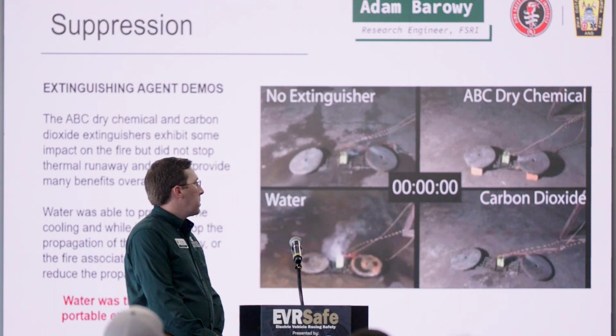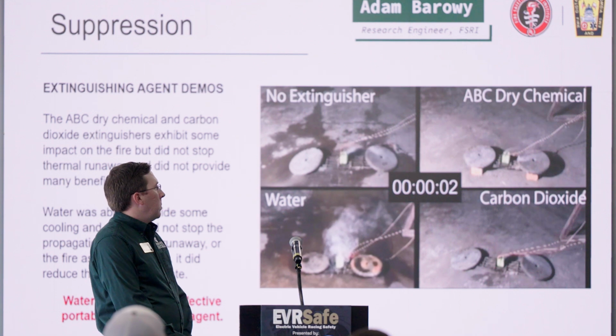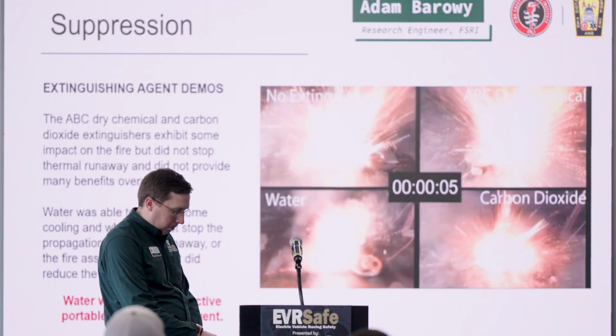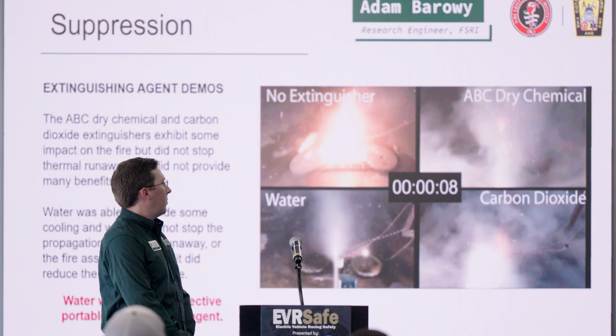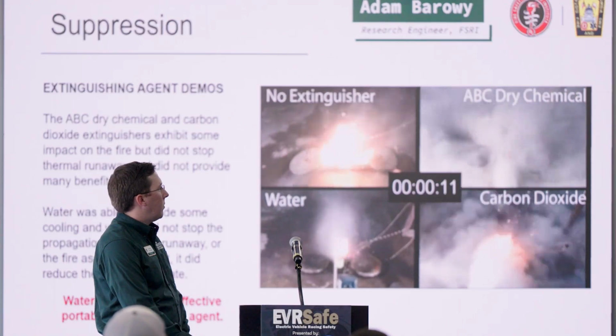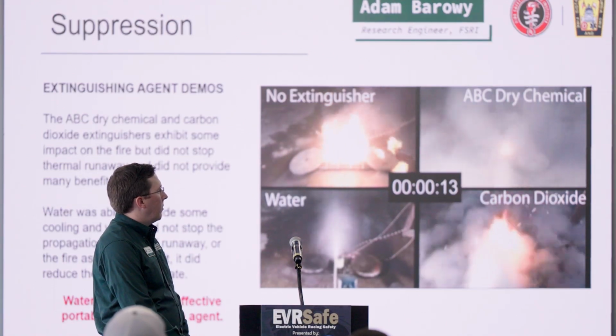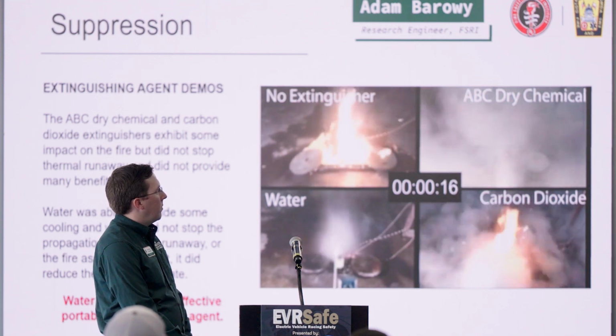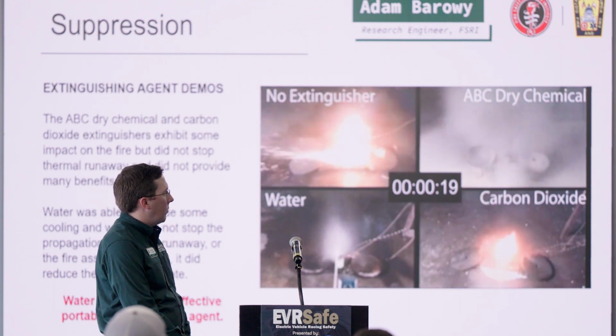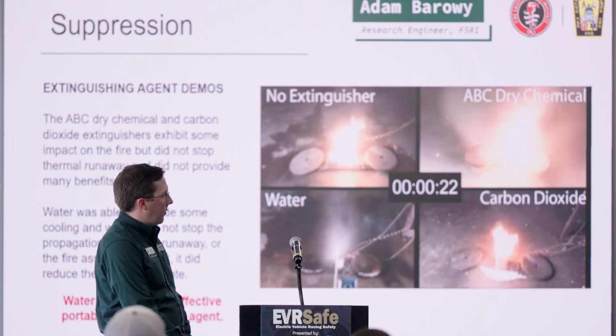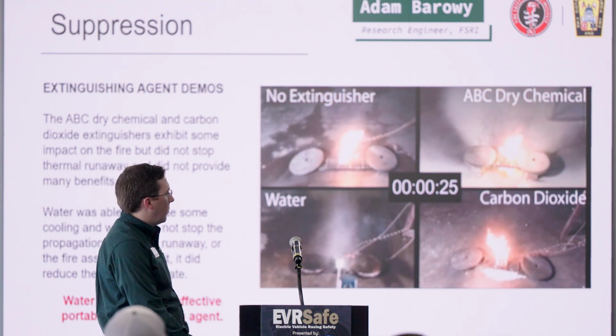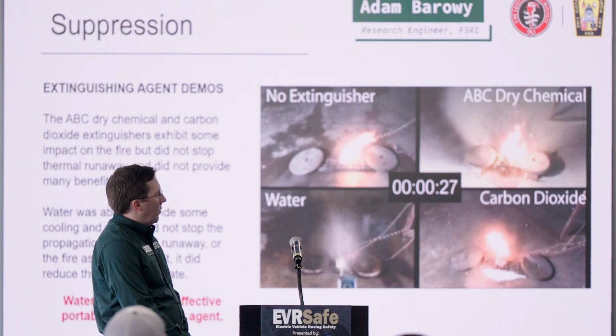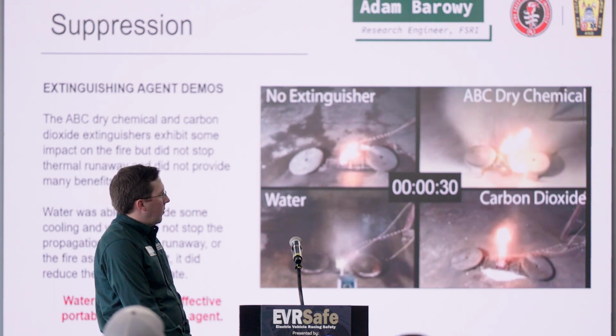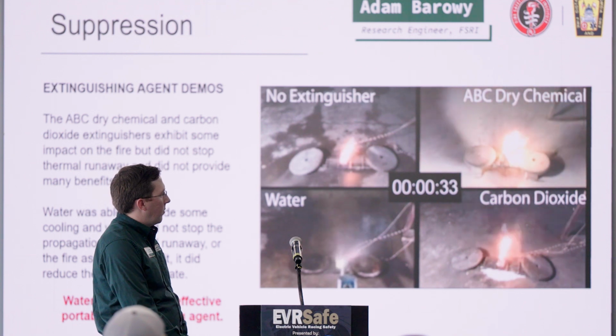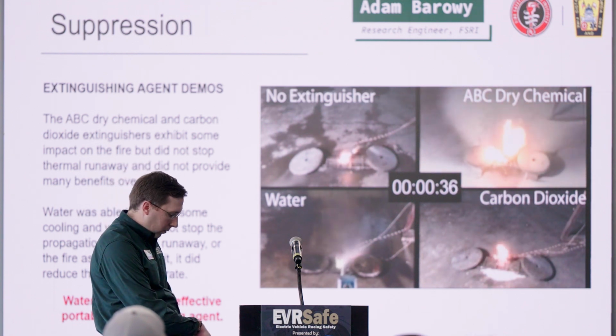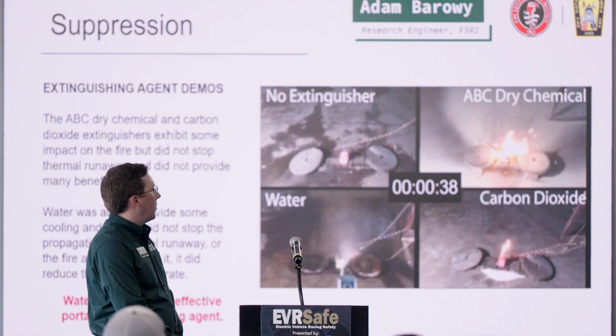So you can basically see for yourself in real time, thermal runaway happens. This is a slightly smaller battery pack, but thermal runaway occurs. We immediately activate whatever the suppression method is, based on the pan there. You can see everything has some effect. It's not that these extinguishing agents don't work on fire or flaming, but they're not addressing the source of flammable gas release, and they're not really stopping propagation of thermal runaway. The thing that does that best is water, because it's a fantastic cooling agent. It's got a high specific heat, it can absorb a lot of energy, it can vaporize. It's all the great things it's always been for firefighting.